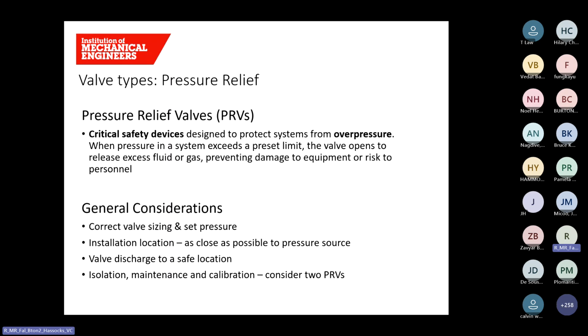Some general considerations include correct valve sizing and set pressure. The valve must be correctly sized to handle the maximum expected flow during overpressure events. The set pressure should match the system's maximum allowable working pressure, and this ensures timely activation. The PRV should be installed as close as possible to the pressure source, and this minimises lag. You should avoid long piping runs that can cause pressure drops or delay valve response. The discharge location should allow for safe venting, and it's worth considering isolation, maintenance and calibration.